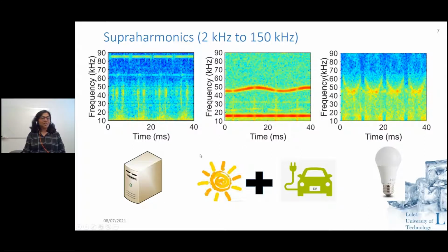A lot of devices which have power electronic converters generate these kinds of distortions, namely harmonics and supraharmonics, or even low frequency harmonics. In this case, for instance, this is a measurement I did with the CPU of a computer, which had a computer power supply switching at 85 kilohertz. This is a spectrogram which shows time versus frequency, so you can see how the supraharmonic varies. In the case of this computer, it is a steady emission at 85 kilohertz, and it is absent at every zero crossing, and again it is there.